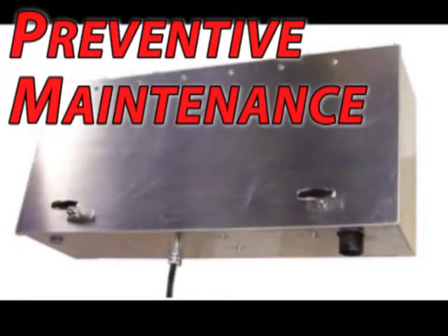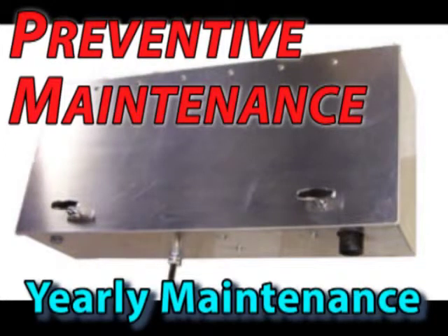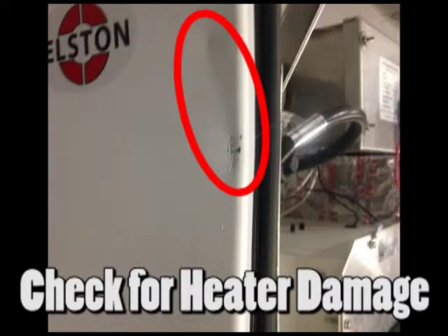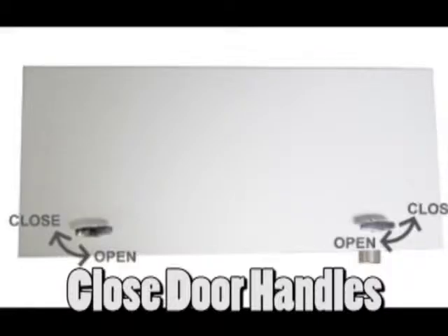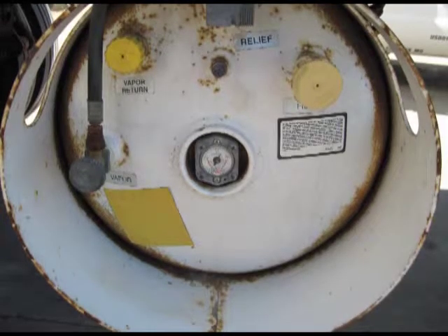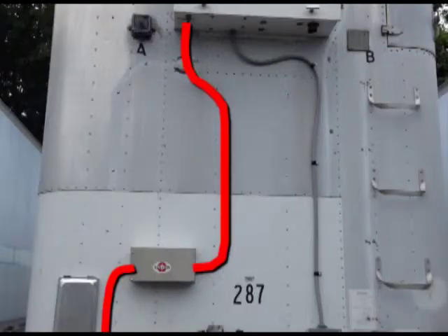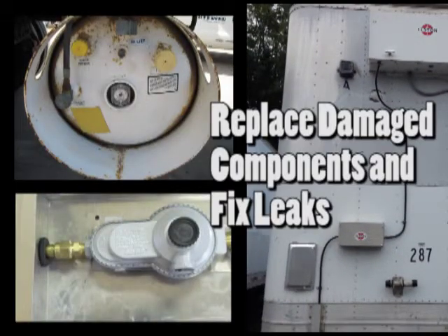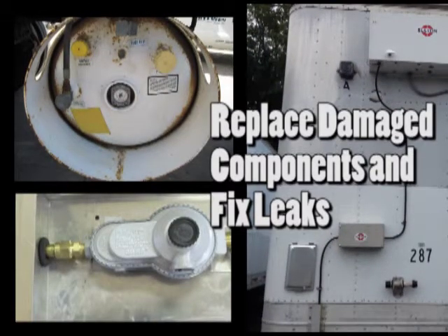Now that you understand the typical operations of the HLC heater, we will inform you of preventive maintenance that is suggested to be completed in order to prolong the operational life of the HLC heater. First, we will discuss what procedures should be conducted on a yearly basis. Check the exterior of the heater for damage. Check that the door handles are in the fully closed position. Carefully inspect the propane tank, regulator, and fuel lines for leaks or damage. Replace any damaged components and fix any leaks.